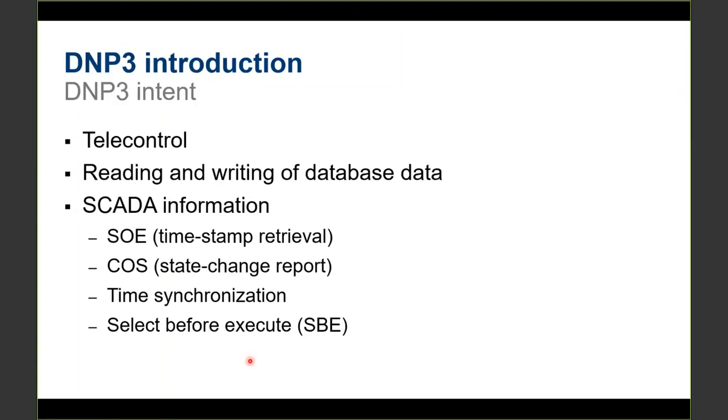The protocol can be applied to provide communication between RTUs and relays, but also can provide communication between the SCADA systems and RTUs. In the first case, communications between RTUs and relays, the RTU will be the master station and the relay will be the slave device.